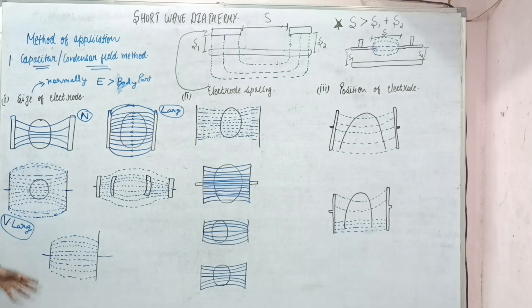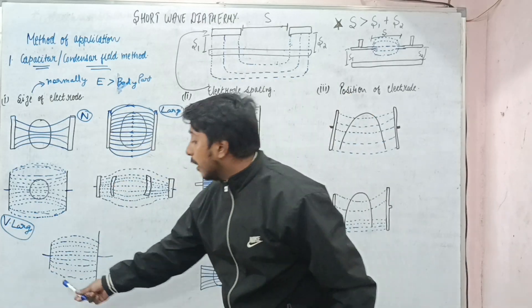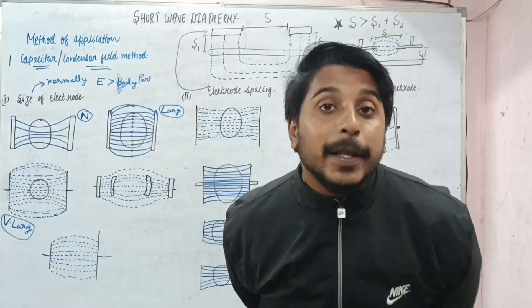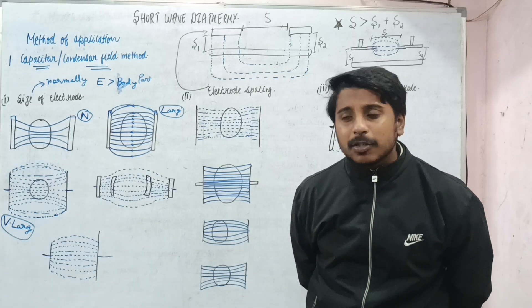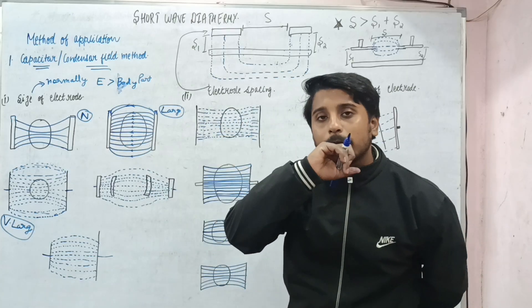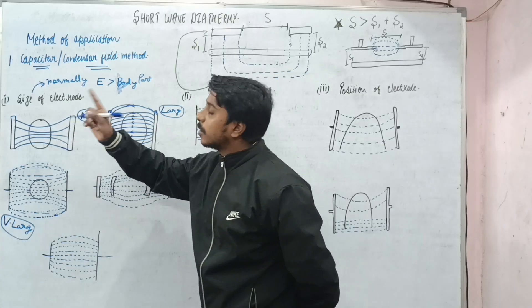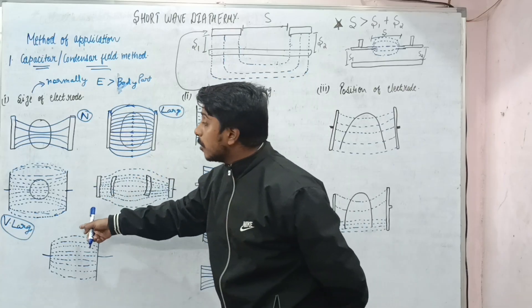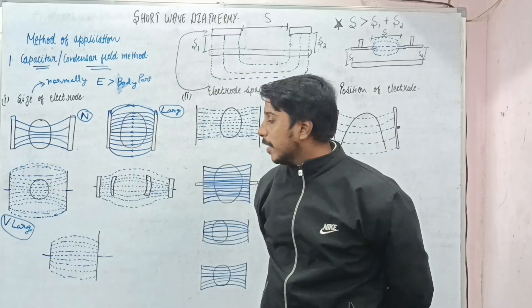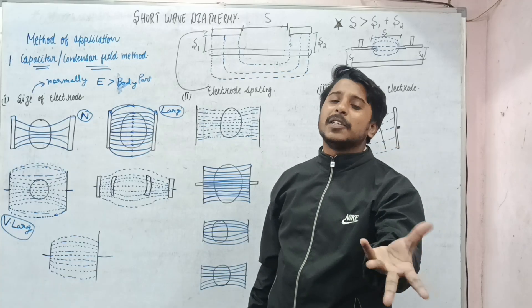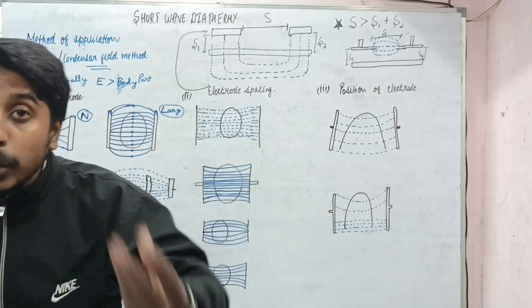If the electrodes are of uneven size — one small, one large — different amounts of charge are required to charge each electrode, which puts an uneven load on the SWD machine. So normally the size should be slightly 1 to 2 cm larger than the tissue, so that lines of force will bend toward it. If very large, most lines of force are wasted; if very small, lines of force spread and cause less heating; if uneven, it puts uneven load on the apparatus.